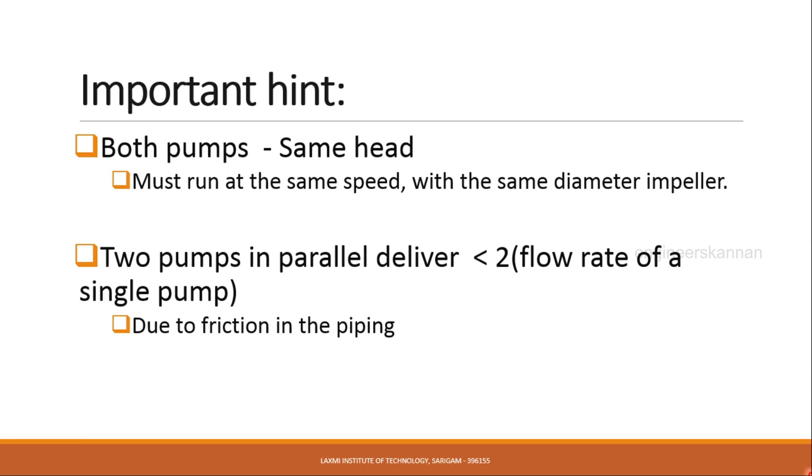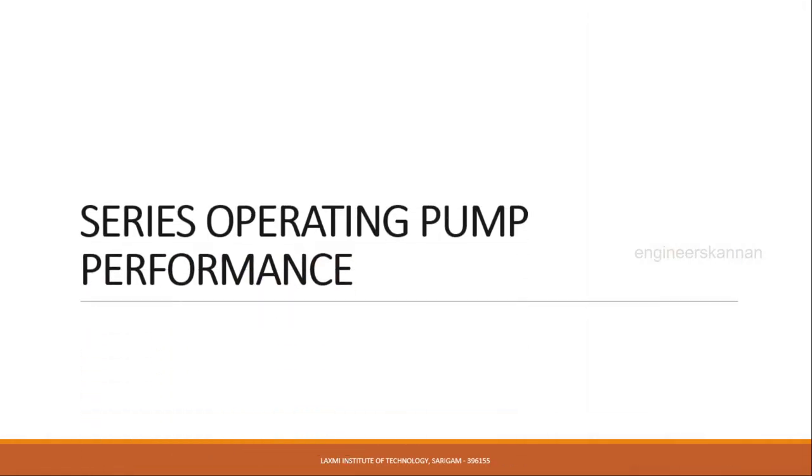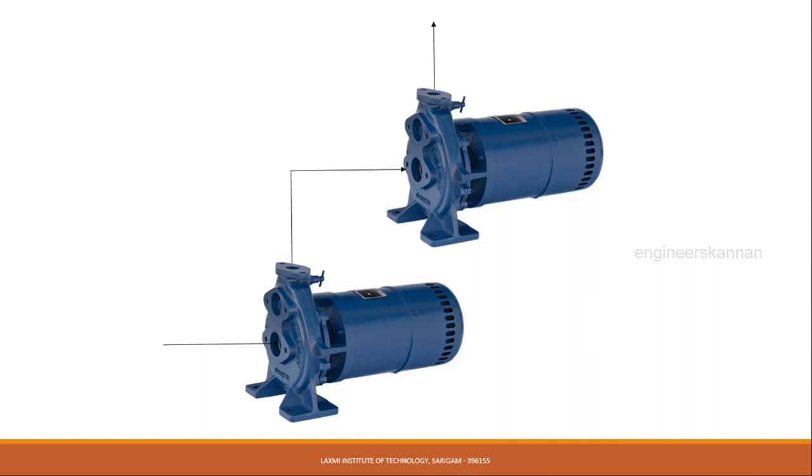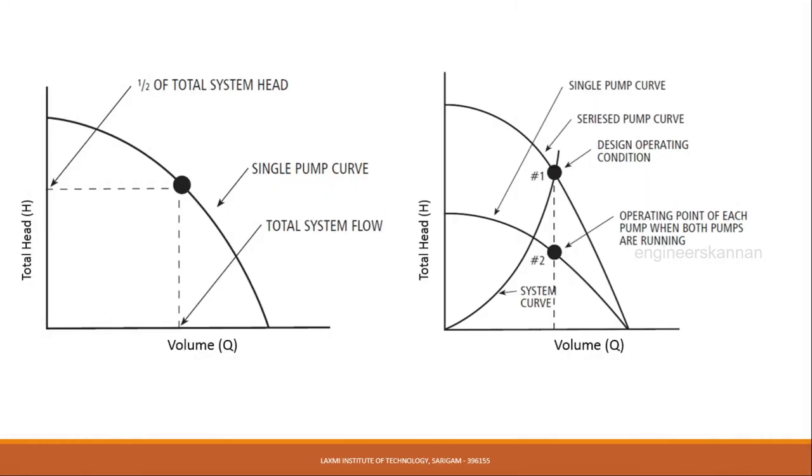Next is series operating performance of pumps. The image represents two pumps connected in series. The major reason pumps are connected in series is to increase the total head delivered, whereas volume remains unchanged. The performance curve clearly indicates that a single pump produces lesser total head, whereas two pumps together can increase the total head from point A to point B.